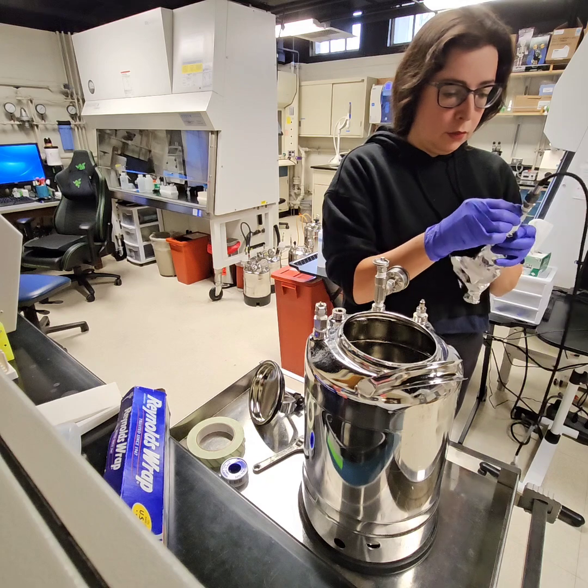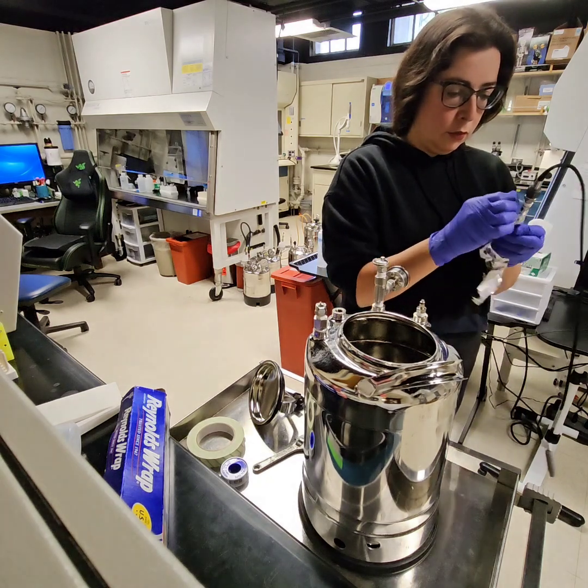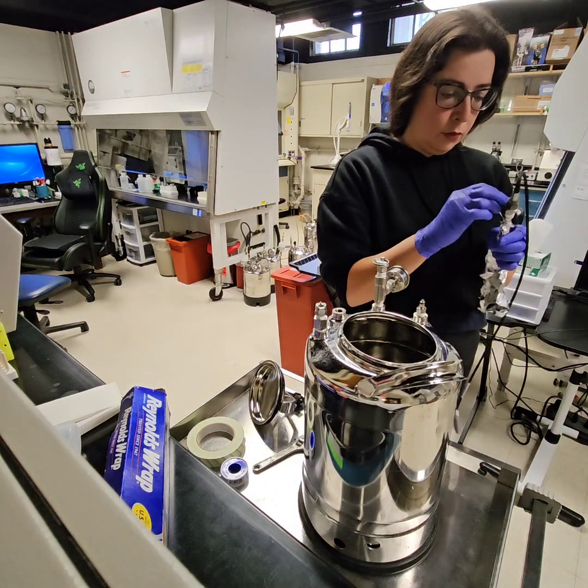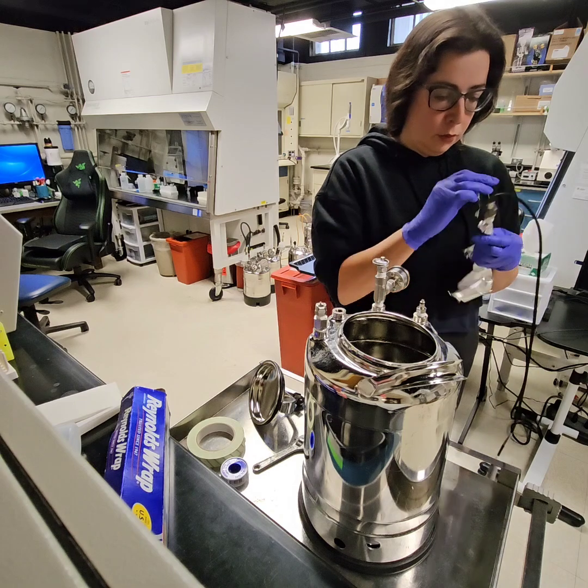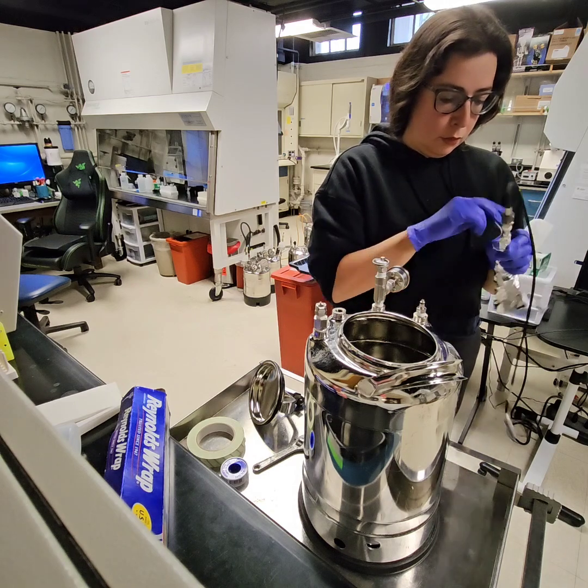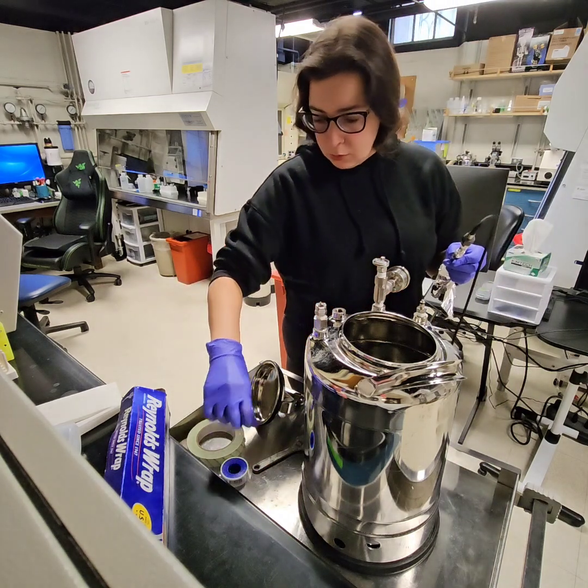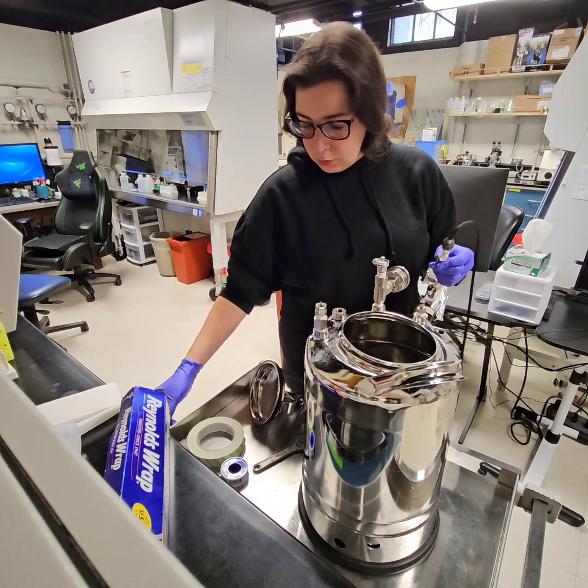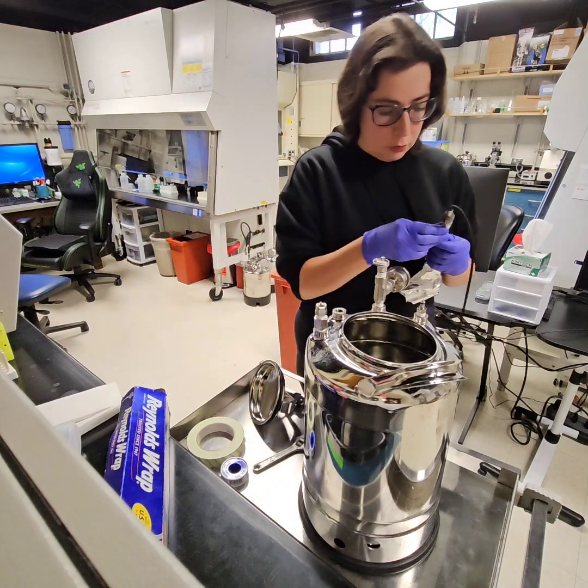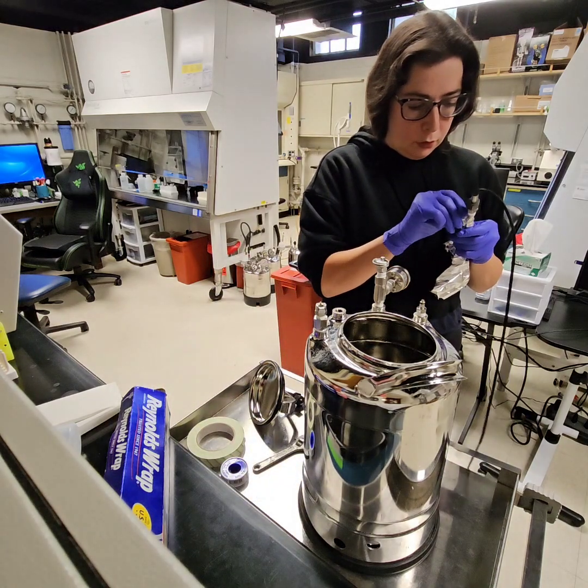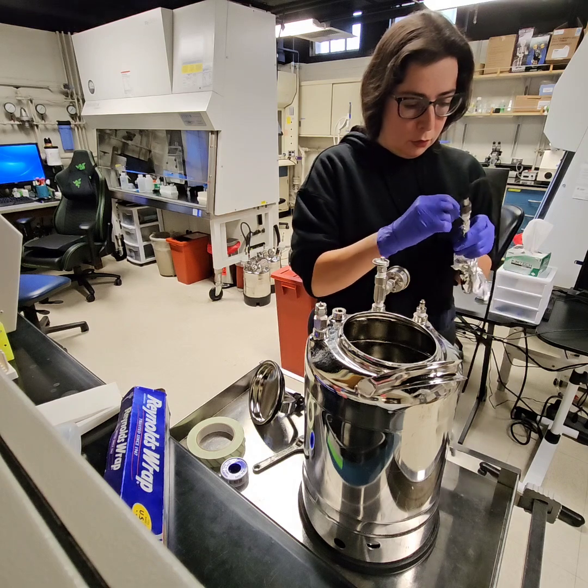But the other thing that I want to do right now is go ahead and remove the old Teflon tape on there. So we're going to need to put new Teflon tape when we put the probe back on, but we don't want to put it on top of the old tape. And if we just keep putting it on top of the old tape, it's just going to create a mess later that could potentially attract rust or other kind of microorganisms to stick there.